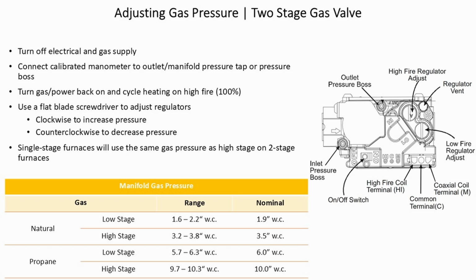Manifold gas pressure. For natural gas, low stage 1.6 to 2.2 inches of water column, nominal 1.9 inches of water column. High stage 3.2 to 3.8 inches water column, nominal 3.5 inches water column. For LP, low stage 5.7 to 6.3 inches water column, nominal 6 inches of water column. High stage 9.7 to 10.3 inches water column, 10 inches of water column is nominal.